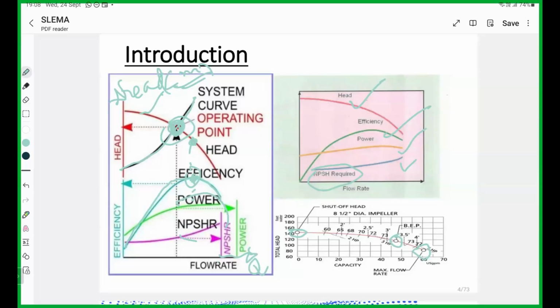Again, I am telling you, the intersection of the system curve and pump curve is the duty point. You have to keep in mind that the duty point is not always the best efficiency point for a centrifugal pump. That is one thing in energy conservation: inefficiencies are there due to mismatching between the best efficiency point and the duty point.